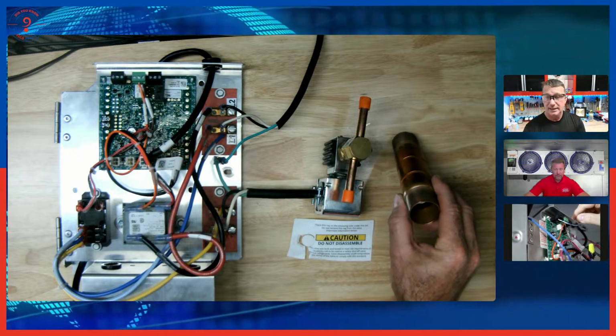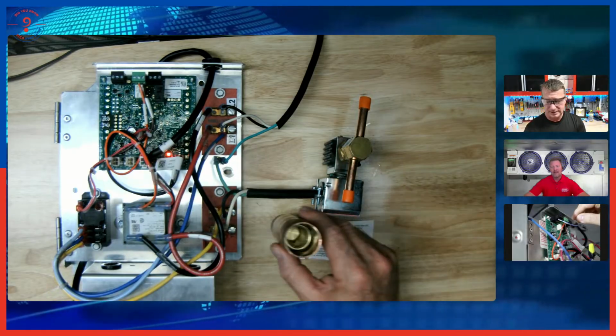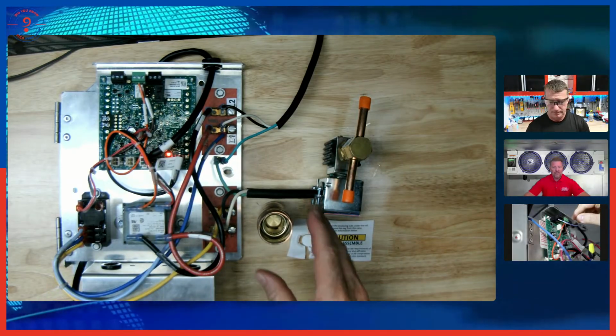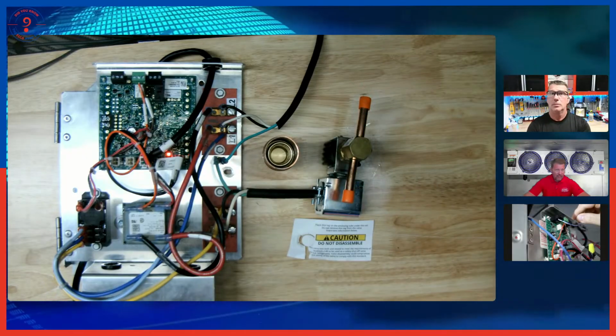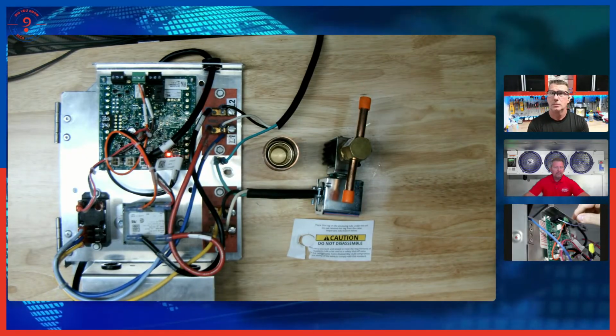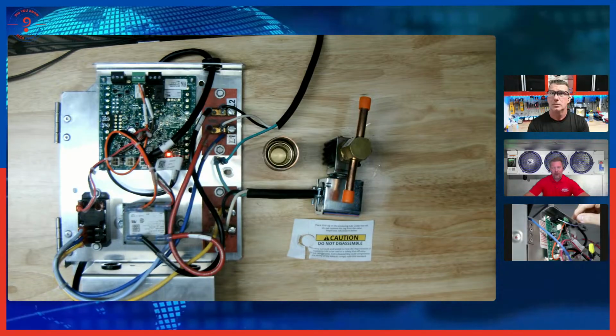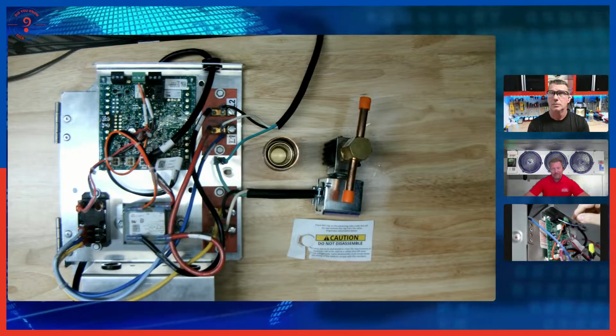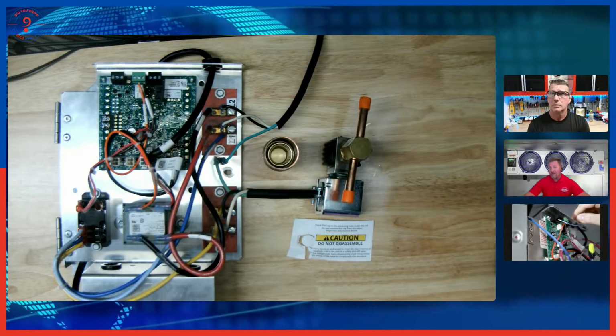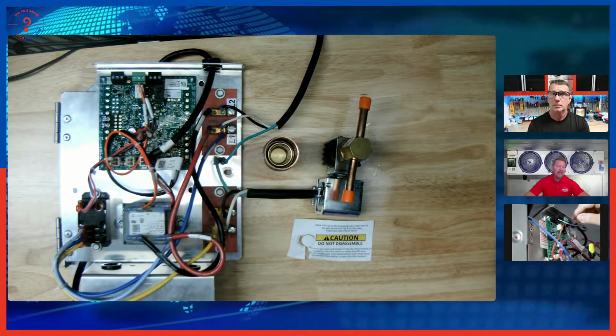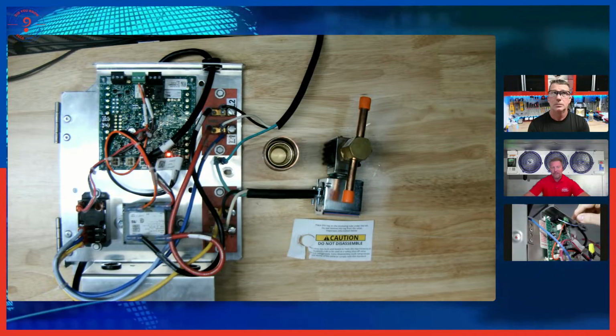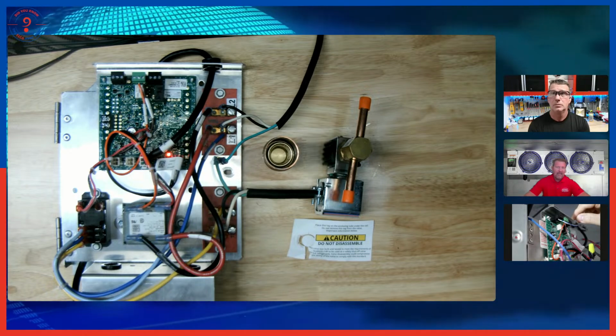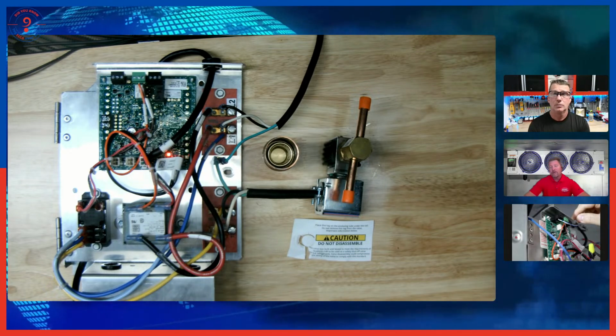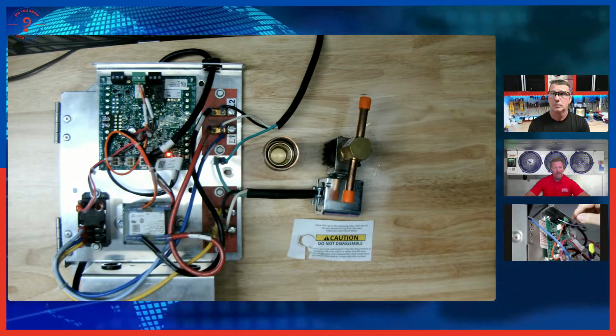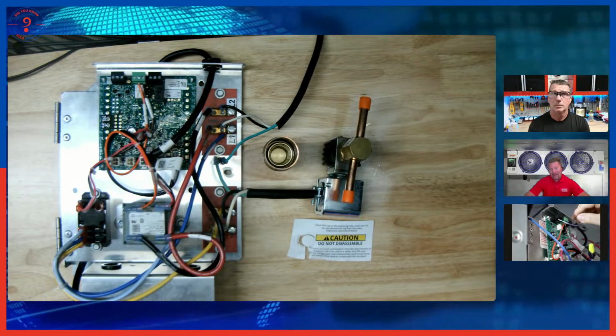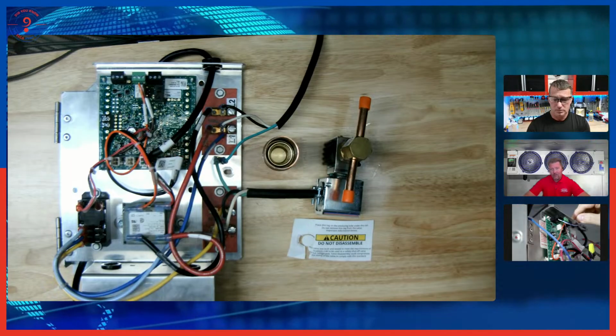And so that is going to be able to isolate our liquid supply. What about the suction side? Let's talk about the requirements on the suction side of our system. So we are required to put a check valve in the suction side, and ordinarily I would say our compressor is going to prevent any kind of bleed back. But let's say we have a very long suction line, something of that nature, or maybe the compressor's getting tired and it bleeds back through a little bit. It happens. Absolutely. This check valve will prevent any partially flammable A2L gas from making its way back into that evaporator, into the walk-in box.